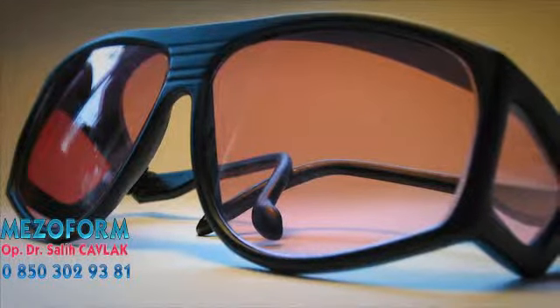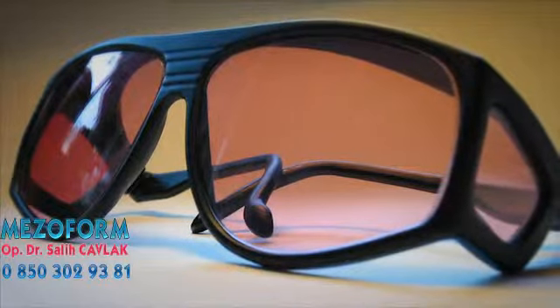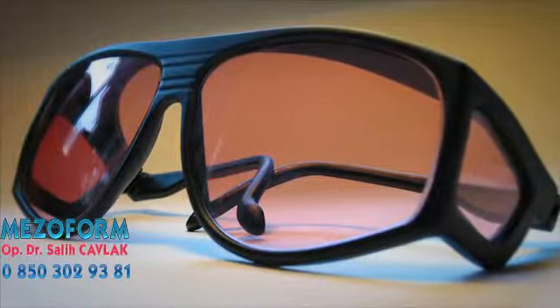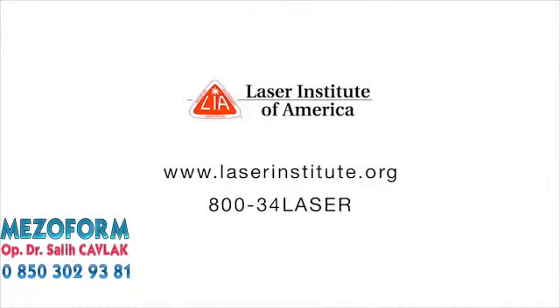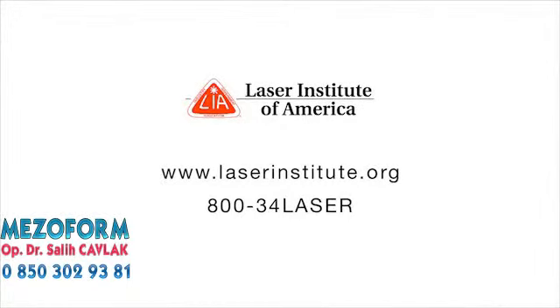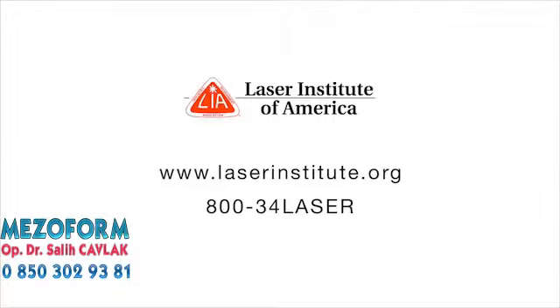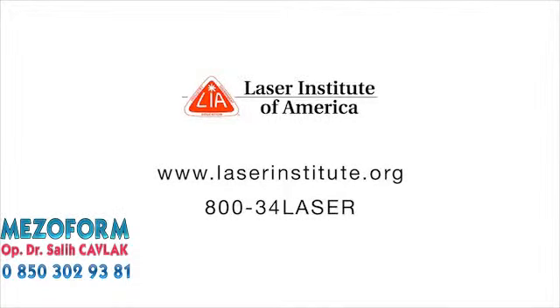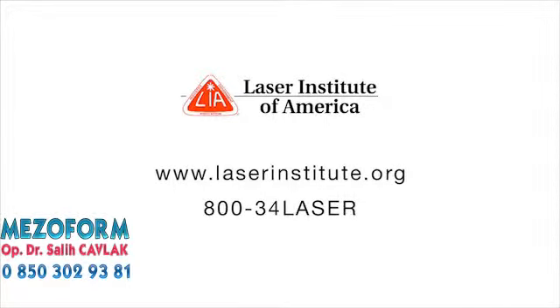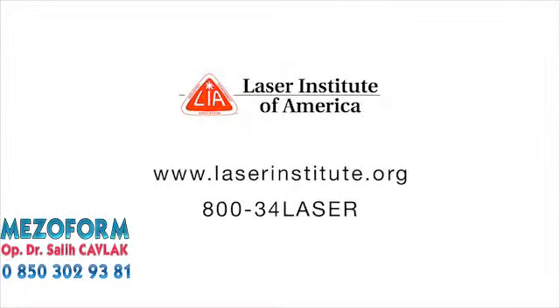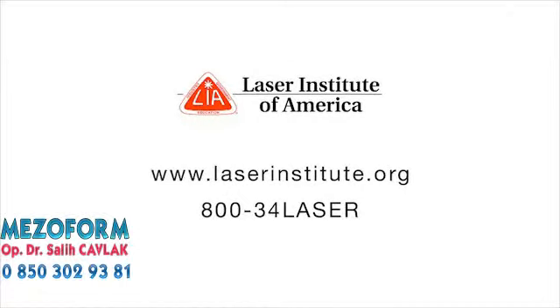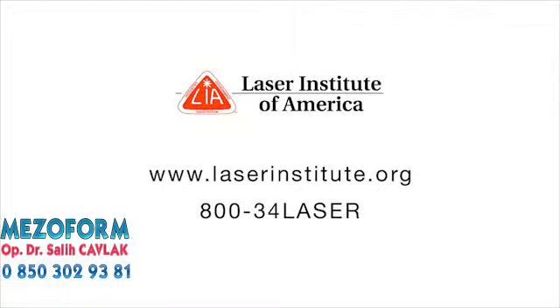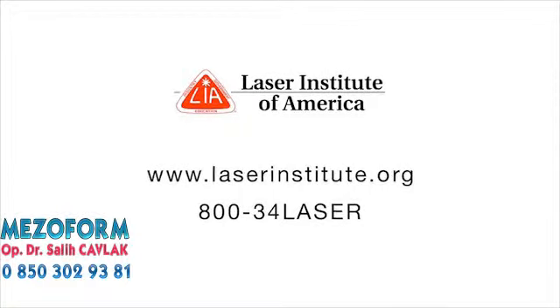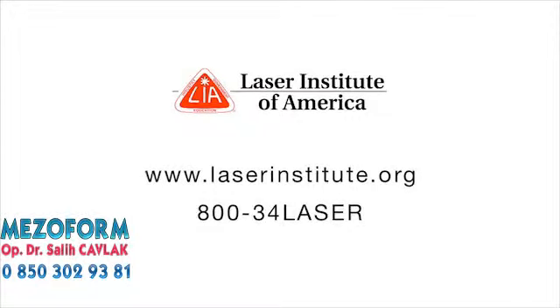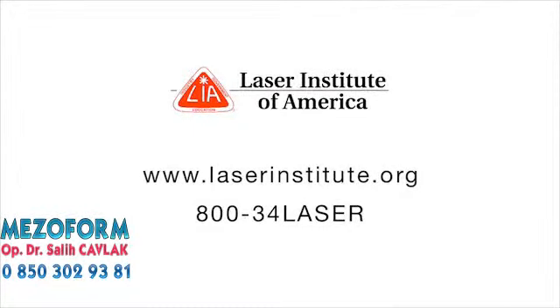All persons operating the LightSheer Duet laser system or in the vicinity of the laser must be aware of the potential hazards. The LightSheer Duet system is classified as a Class 4 laser by the Center for Devices and Radiological Health and as a Class 4 laser by the European Laser Safety Standard EN 60825-1. For more information, refer to the Laser Institute of America at 1-800-34-LASER. That's 1-800-34-LASER, for current American National Standards Institute and Occupational Safety and Health Administration standards.